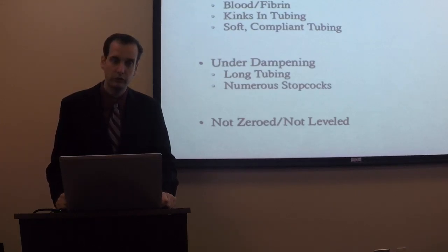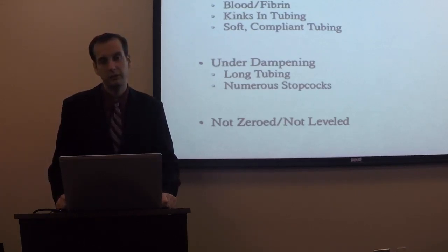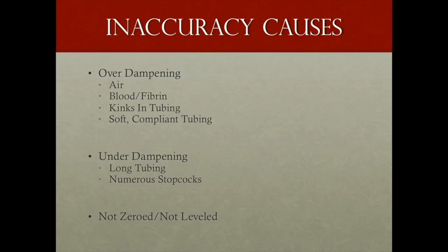If you feel normal intravenous tubing and then feel arterial line tubing, you'll see the arterial line tubing is much harder. If you use tubing meant for venous fluid insertion in an arterial line system, you will get a significantly dampened waveform, as the softer, more compliant tubing will absorb more of the pressure.